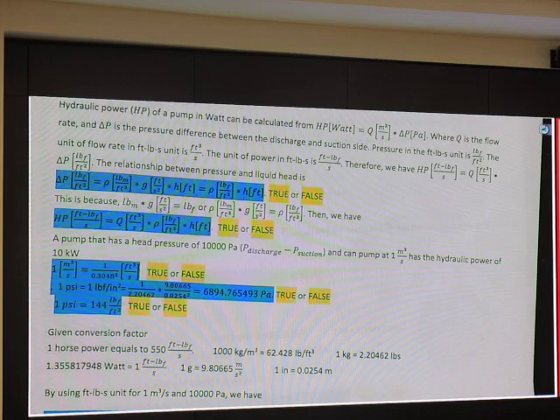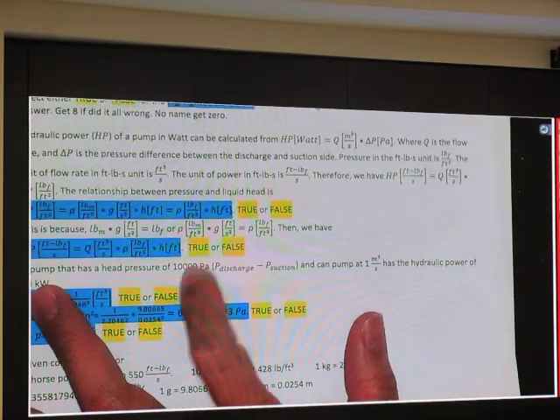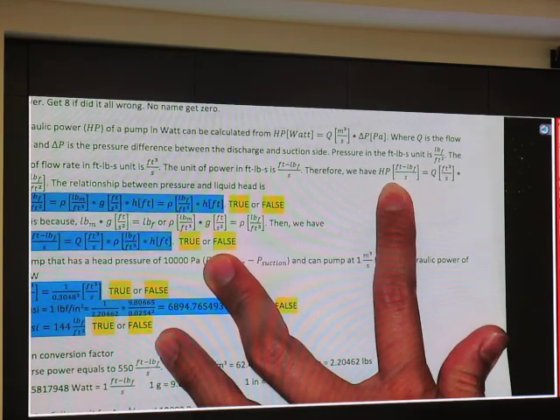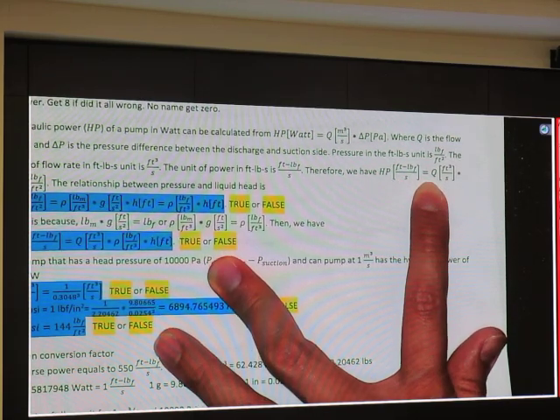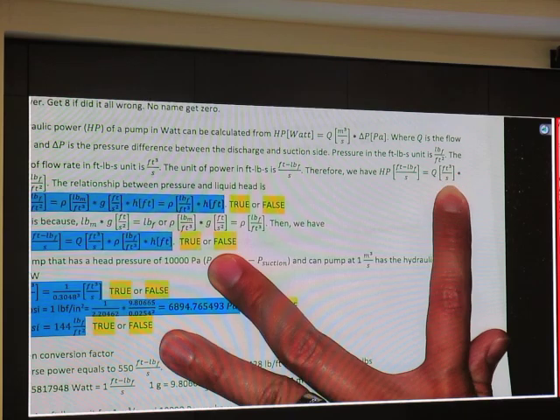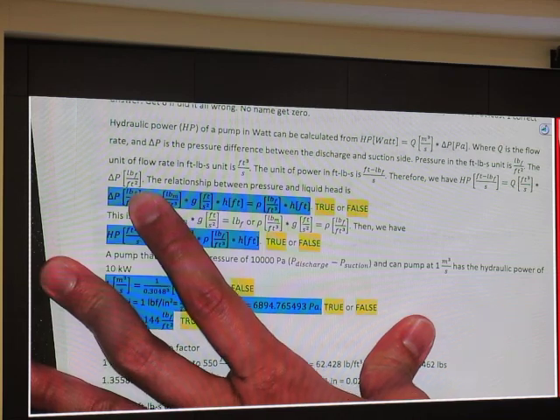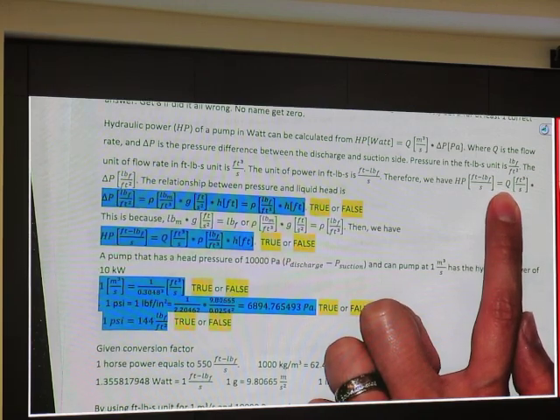The unit of flow rate will be cubic foot per second. The unit of power in engineering units is foot pound force per second. Then we have hydraulic power equal to flow rate, cubic foot per second, multiplied by delta P, pound force per square foot. Not psi. So when we have this relationship, the coefficient is one, no coefficient.